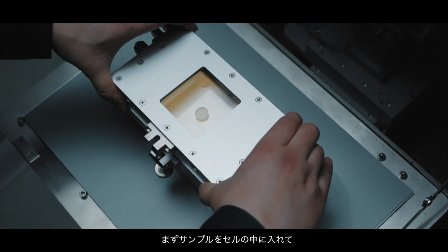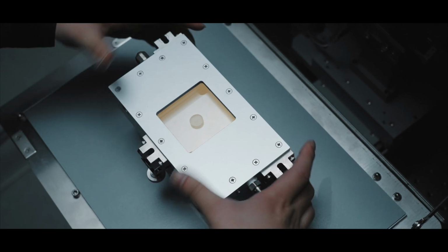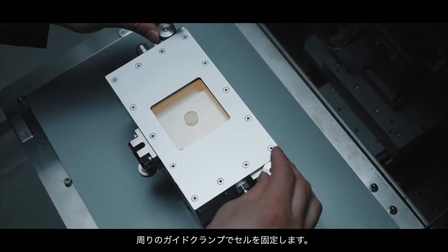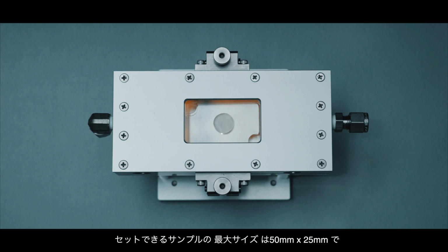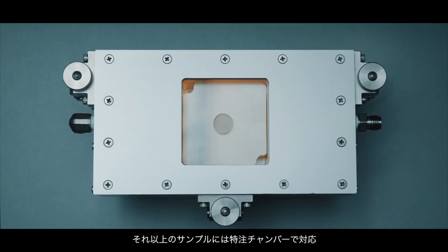Section 1, Operation. First, set the sample in the sample cell chamber and secure with guide clamps. Maximum size for samples that can be set is 50 millimeters by 25 millimeters. If the size is larger than that, we can handle it by making a customized cell chamber to your needs.